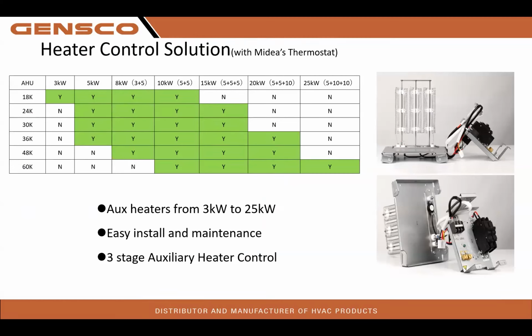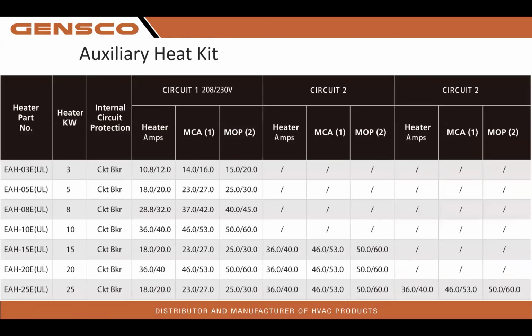We are offering 5 to 25 kW. And this is a description on what size heat kits we can install in different air handlers. So you'll notice that our 36K model, we can't put a 3 kW in there, but we can go 5 to 20 kW. The only piece of equipment is the 5-ton unit that we can put a 25 kW heat kit in. Here is our look at our auxiliary heat kit, max circuit capacity, heater amps, internal circuit protection. There's our kilowatts and our part numbers. You're just merely going to let the counter know what kW heat kit you want, and they will round it up for you.